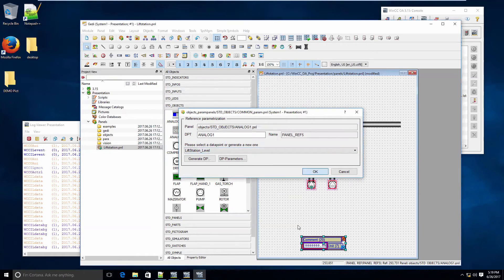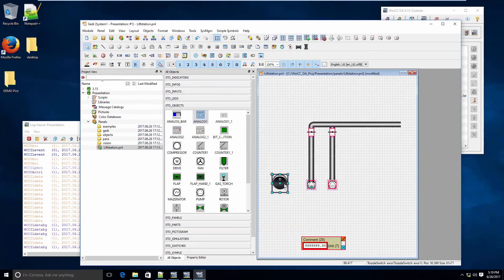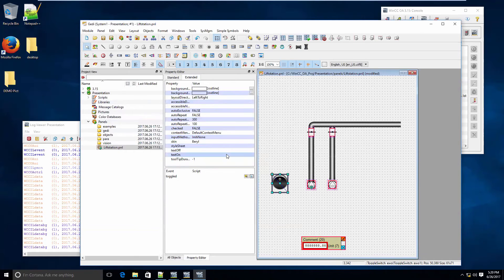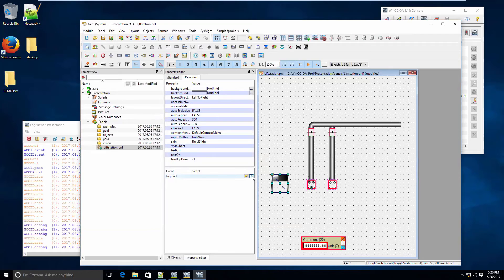All the control should happen in the PLC; when I turn a pump on I'm just going to simulate the value of the level, which may be rising or falling depending upon the simulator. We're going to add a switch to turn the pumps on using an extended widget object — we'll change the toggle view by looking at an extended property of that EWO. Then we'll put some scripting behind it: when the value toggles on, we get the current value of pump one's state, store it in an internal variable, and toggle that value.